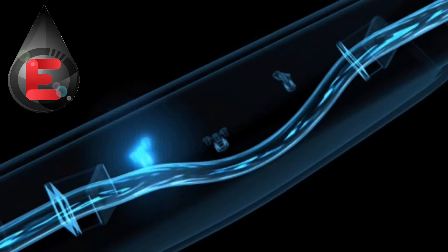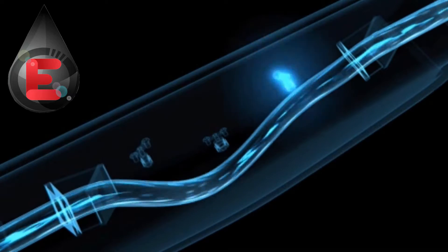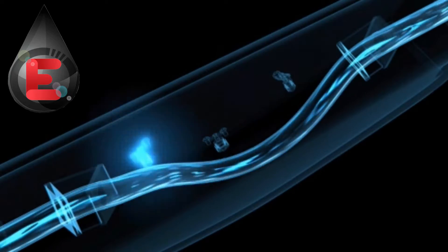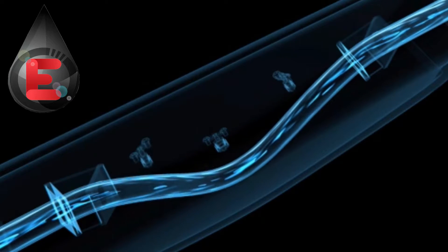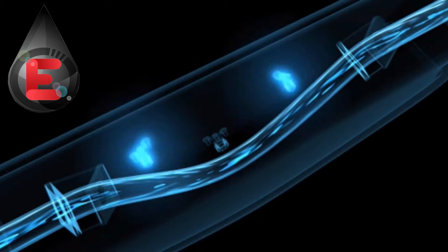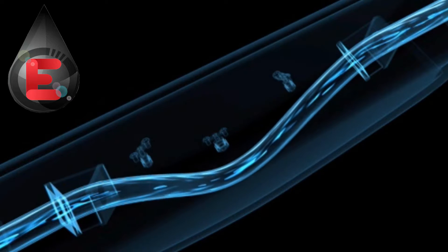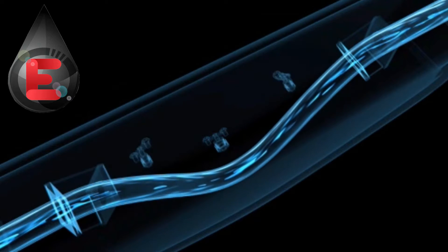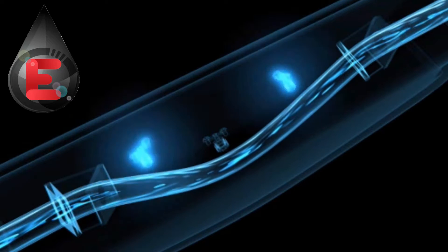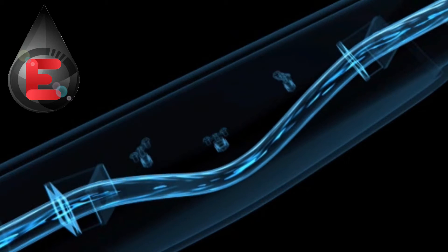The application of the Coriolis measuring principle doesn't stop here. It can also be used to simultaneously determine the density of the flowing fluid. To do so, the sensors also register the oscillating frequency, in other words, how often the measuring tube moves back and forth in one second.